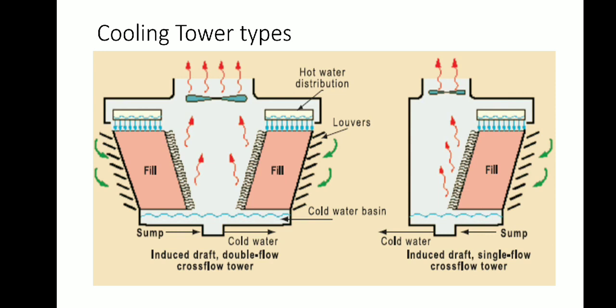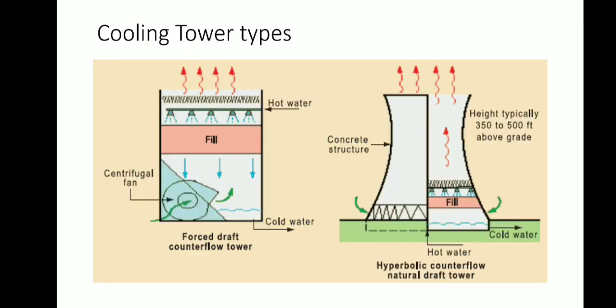Mechanical draft towers are available in a large range of capacities. Normal capacity ranges from approximately 10 tons, or 2.5 metric cube per hour flow, to several thousand tons and metric cube per hour. Towers can be factory built or field erected. For example, concrete towers are only field erected. Many towers are constructed so that they can be grouped together to achieve the desired capacity.